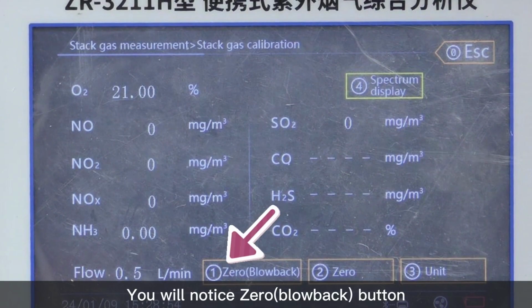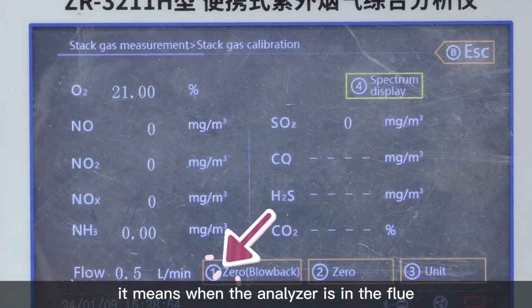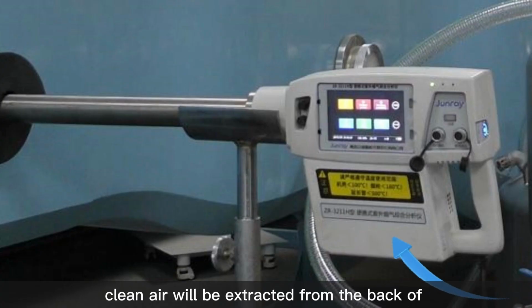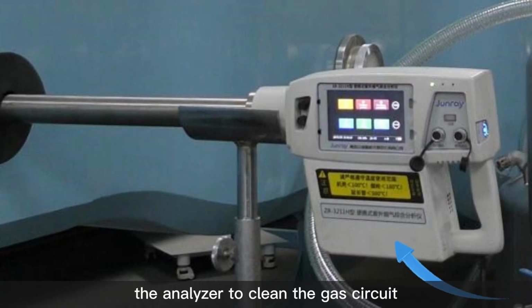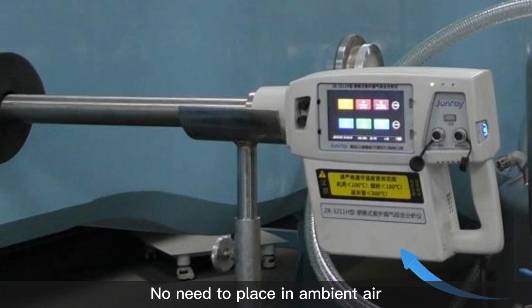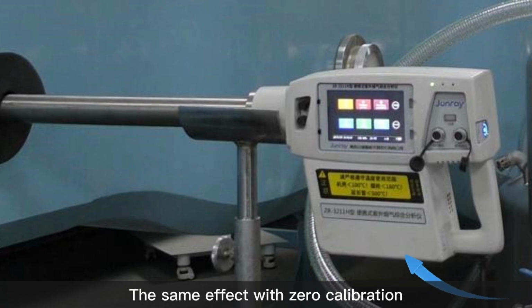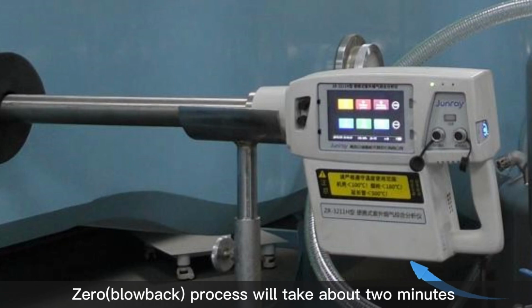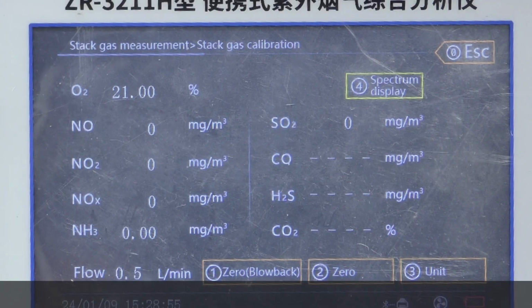Here Zero Calibration is completed. You will notice Zero Blowback button. It means when the analyzer is in the flue, clean air will be extracted from the back of the analyzer to clean the gas circuit. No need to place in ambient air. The same effect with Zero Calibration. Zero Blowback process will take about 2 minutes.